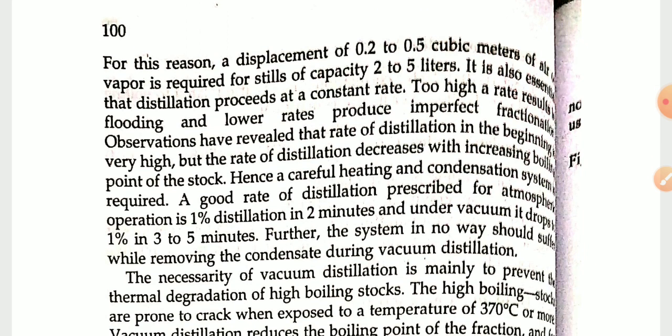The temperature of fractions leaving the condenser system is monitored. The condensate collects into a graduated cylinder connected to vacuum-producing devices. The vacuum device must have sufficient displacement capacity to ensure satisfactory operations. For this reason, a displacement of 0.2 to 0.5 cubic meters of air vapor is required for a still capacity of 2 to 5 liters. It is also ensured that the distillation proceeds at a constant rate — too high a rate results in flooding and a lower rate produces imperfect fractionation. The rate of distillation decreases with increasing boiling point of the stocks, hence careful heating and condensation are required.